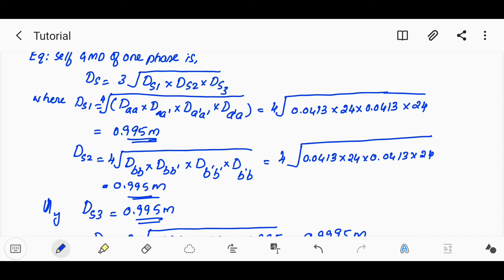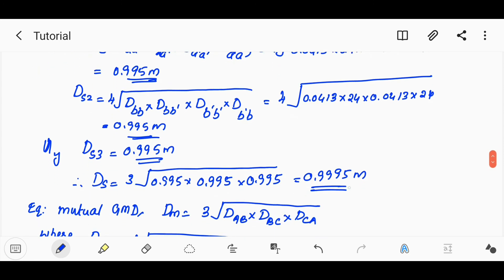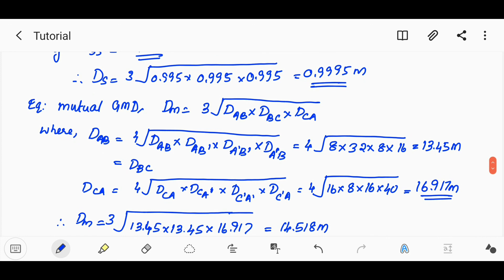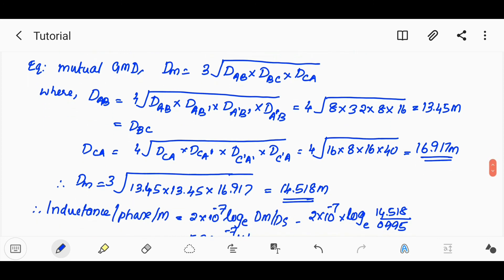DS1 and DS3 are very similar. The equivalent mutual GMD Dm is computed using DAB, DBC, and DCA. DAB = 4th root of the product, giving 13.451 m. DBC = 16.917 m, Dm = 14.518 m. These values are used to compute Dm.